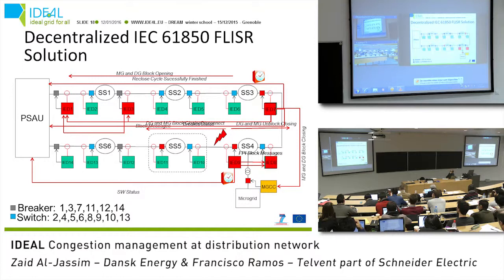So now we can act here, following exactly the same logic, metric function, etc. This device will detect that it is the closest to the fault, so it will open, and now we can restore this part of the grid and also allow this microgrid operation. So we will send messages, updating the situation, and then we will connect the grid again.